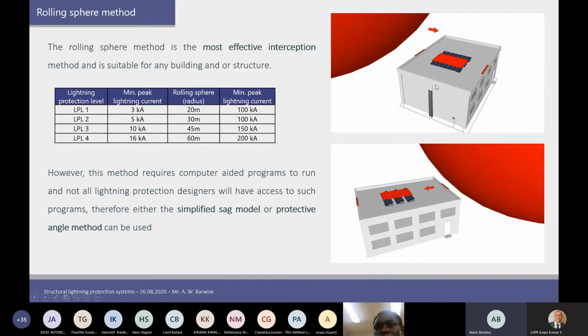If you see on the right, we have this building now, and the rolling sphere method basically says we have a sized sphere. So here you can see the sizes. The radius of the sphere is 20 meters for level 1 and 60 meters for level 4. So we would take this sphere, so a big round ball, make it as large as the lightning level would request us to, and then we have to roll this ball over the building. As you can see here on the top, so we first roll it from west to east, and then maybe from north to south. And wherever the ball has touched the surface of this structure or building, those are then identified as points where lightning could possibly attach. So that's where lightning would strike or could strike.